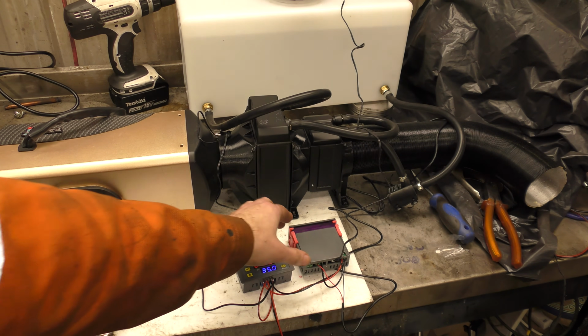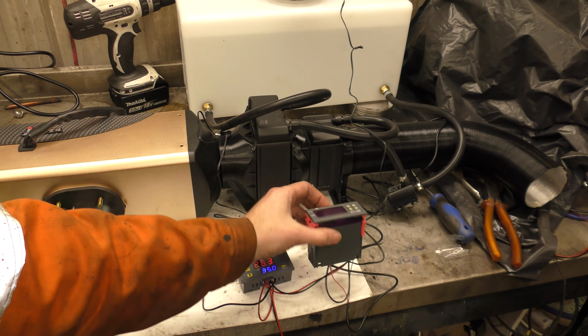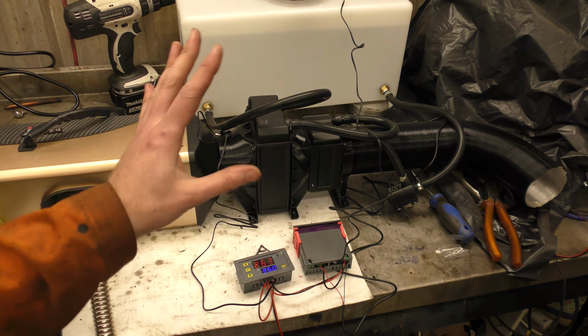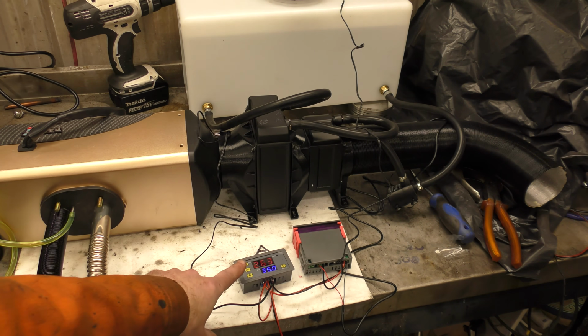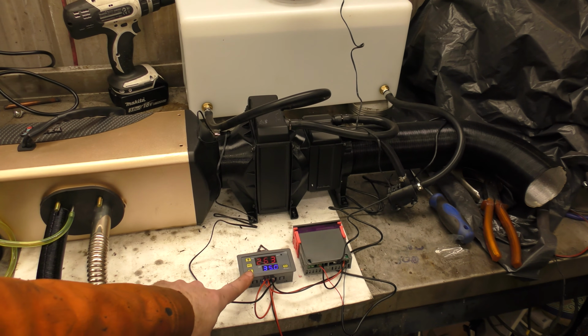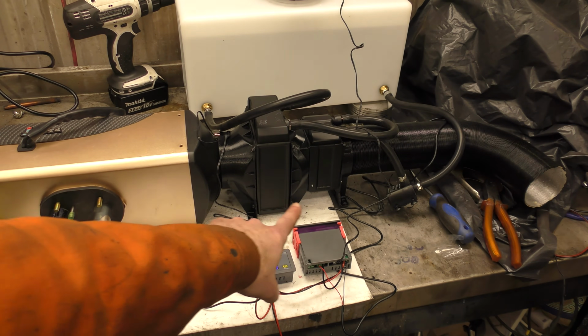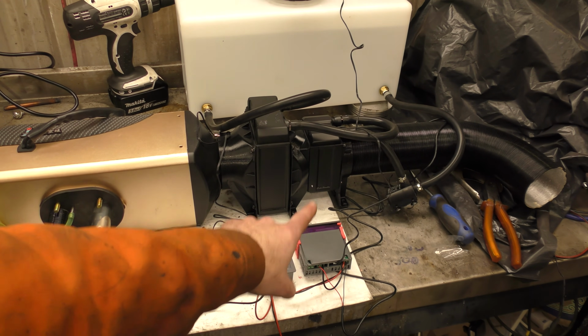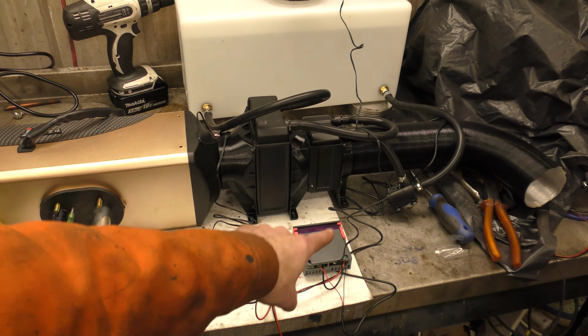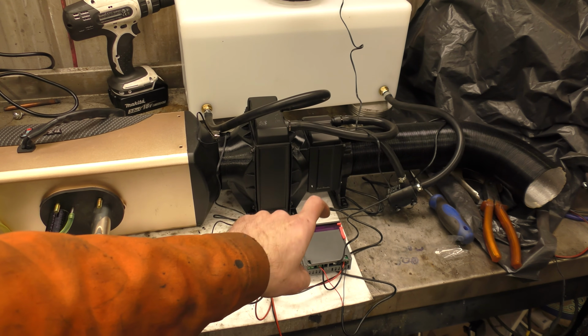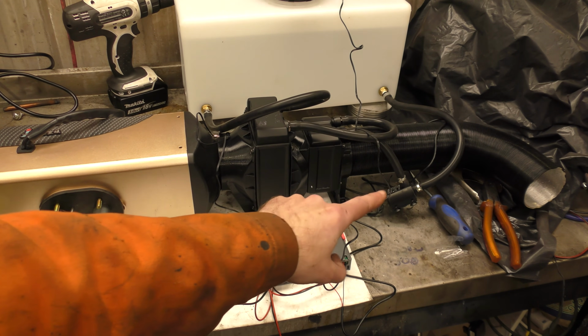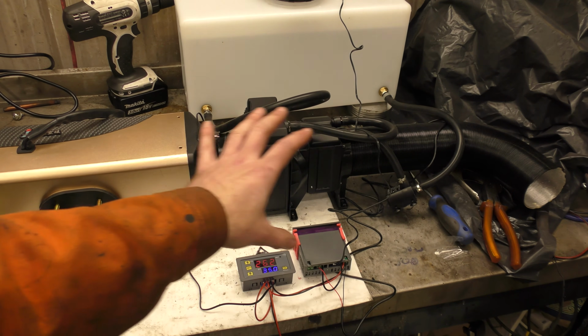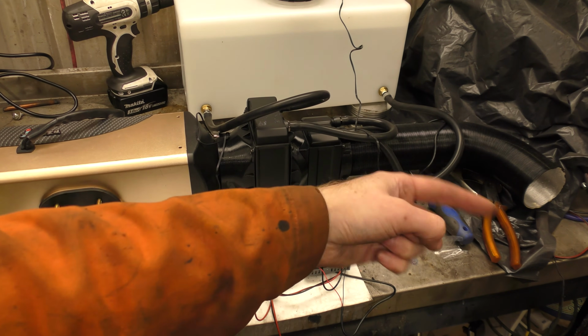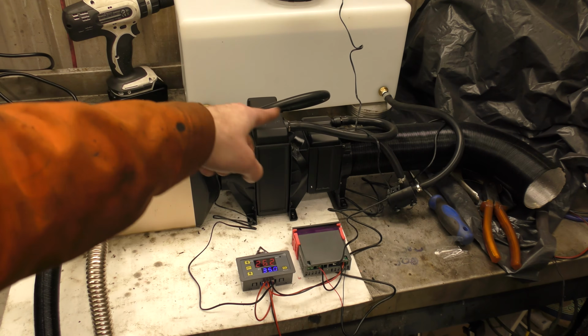I've just used the STC-1000 I had left over from another project. This controller is set to 35 degrees, so when the air temperature gets to 35 degrees it turns this one on, which turns on the pump. When the other one gets to 55 degrees, it turns the pump off, so no more hot water is produced by the system. Hot air will then exit there, and your tank should be at 55 degrees.